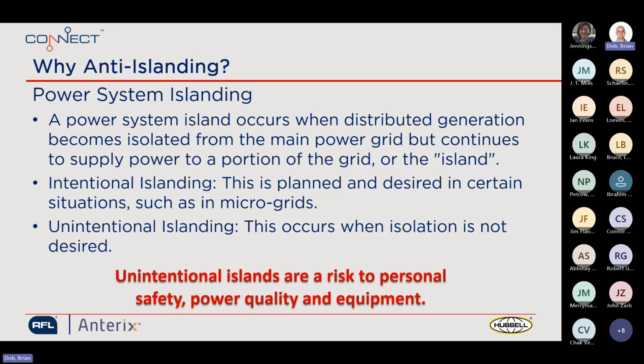There are 2 types of islanding, what's called intentional islanding or unintentional islanding. Intentional islanding would be something like a microgrid, where it can operate independent from the grid. And you have unintentional islanding, where obviously this is not an intended situation, but where the generation can become isolated and continue to backfeed power into this island, not connected to the utility substation.